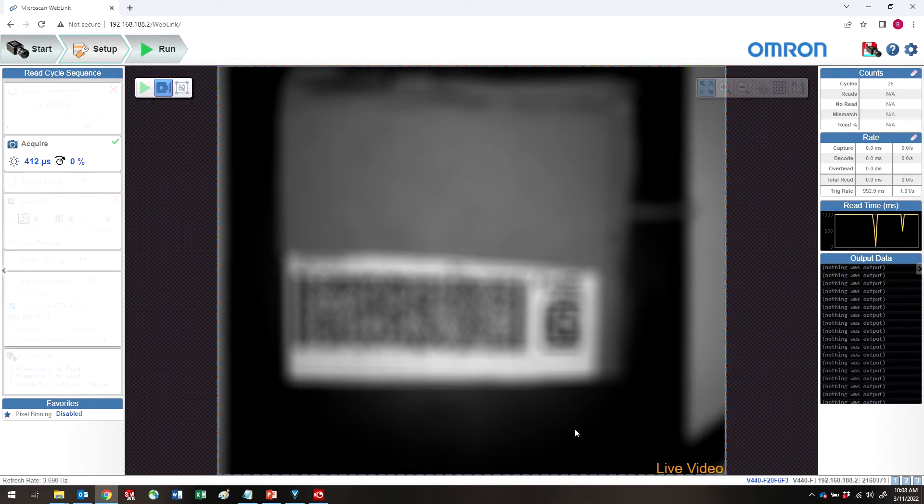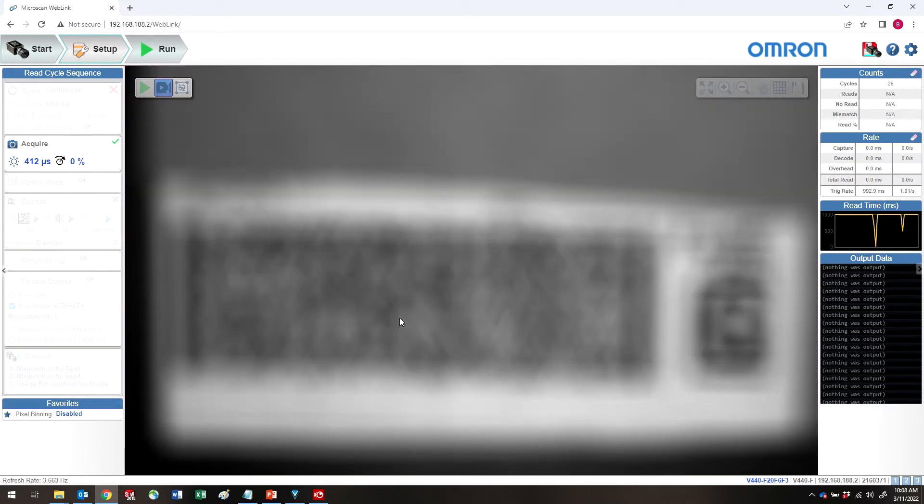You now want to focus your lens. If your lighting is not right to start off with, in this case it's too bright, you select the Quick Photometry selection. It will automatically change the intensity. Then, click live video. And you can zoom in using the wheel on your mouse to get a better focus. Then you adjust the focusing lens for the sharpest image.